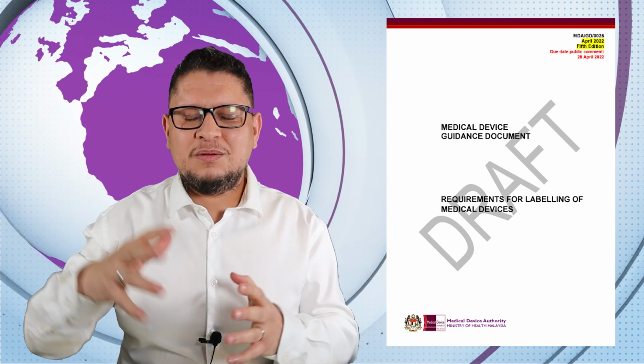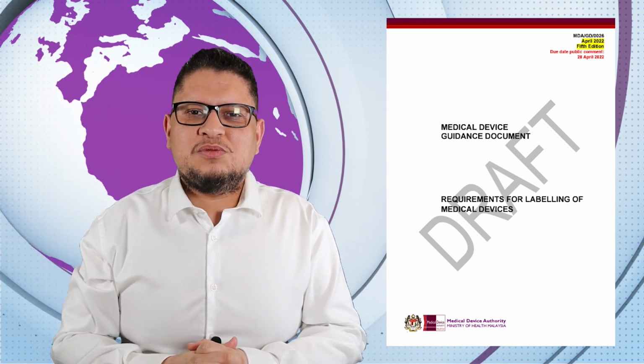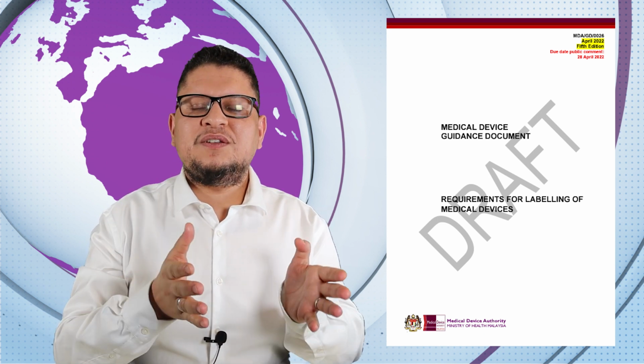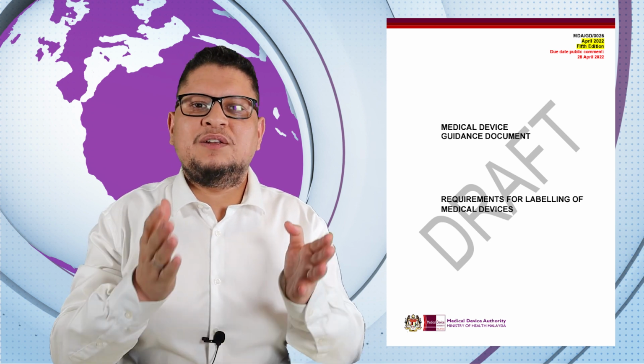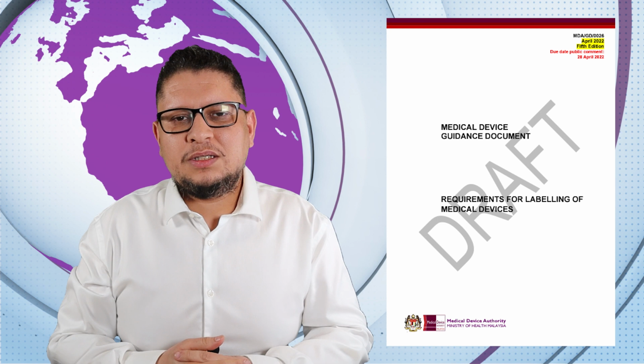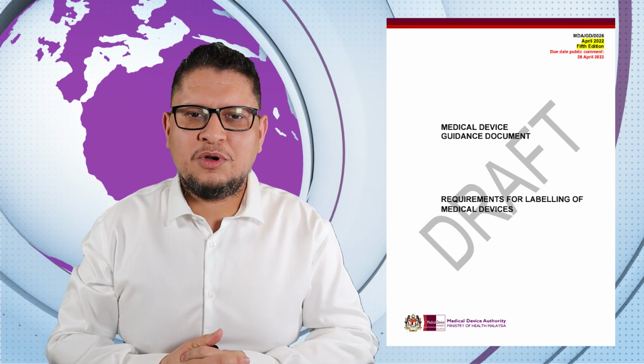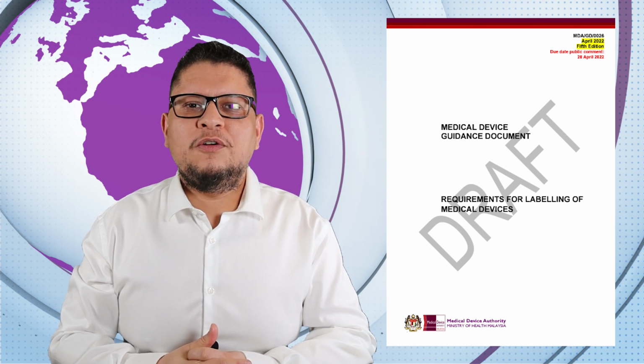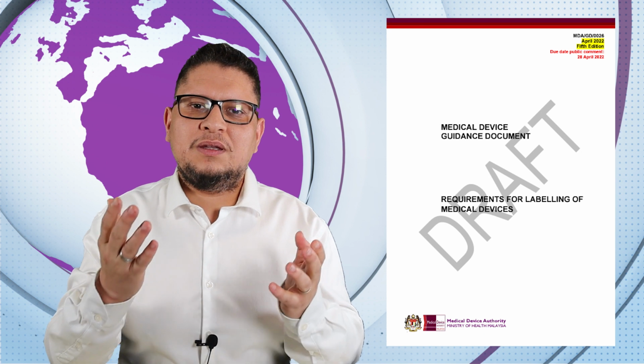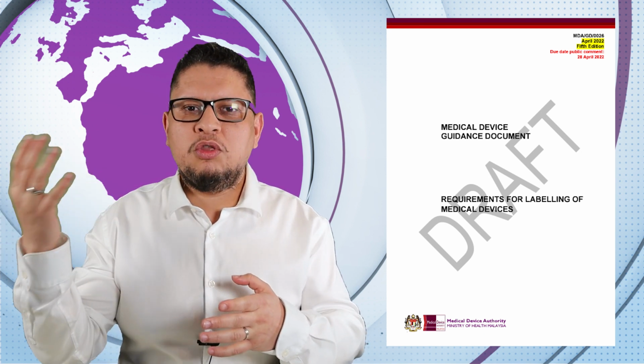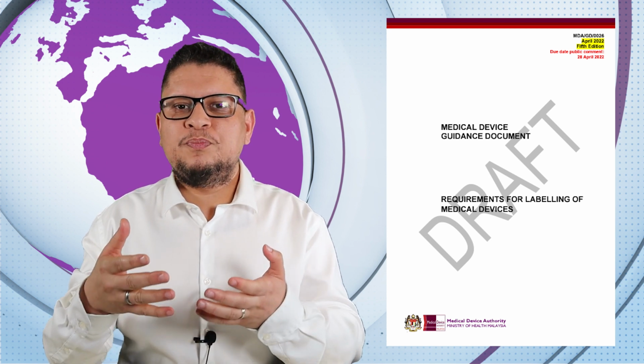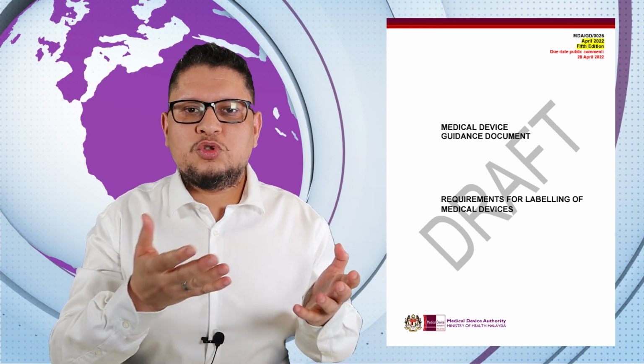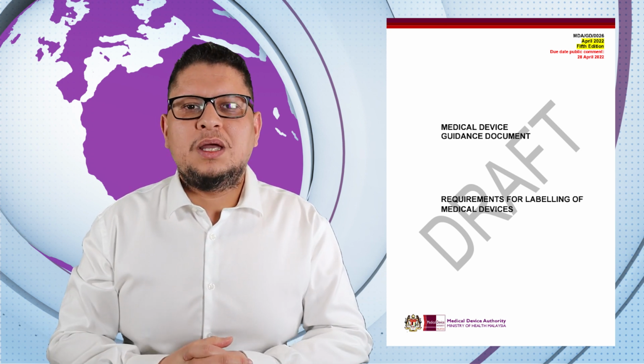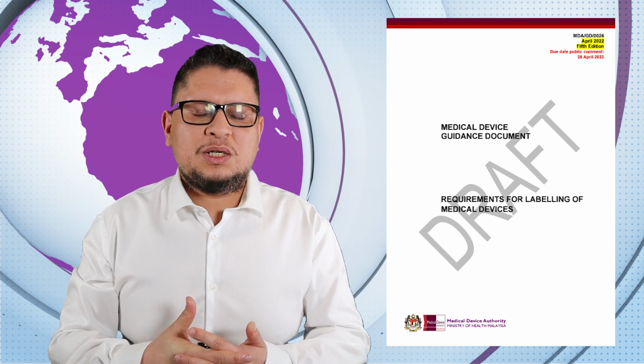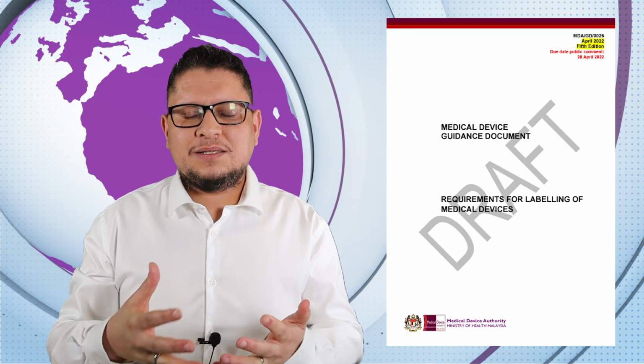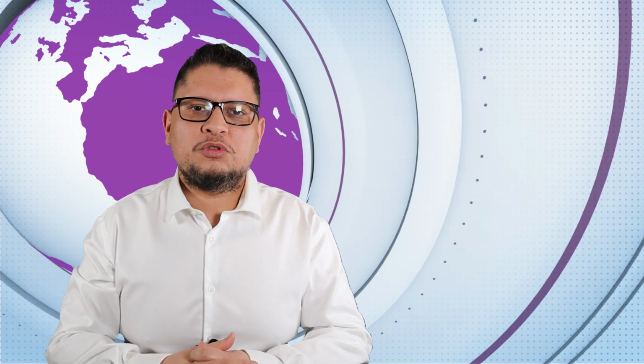Because then your label is big, gigantic. So my advice is really to try to set up specific references or specific labels for certain countries and some for others. But I know it's not easy, and it's more of a logistic job, if I can say, to think about that. But this is the best way to avoid any issue on a certain market, and to avoid that changing the label impacts some registration in other countries. Because as soon as you change the label, you may have to resubmit the registration in countries that normally should not be impacted by this label, but you have to do that. So labeling requirements are really critical for you to check and verify, and as I've said, to be compliant for each of the regions where you are selling your products.